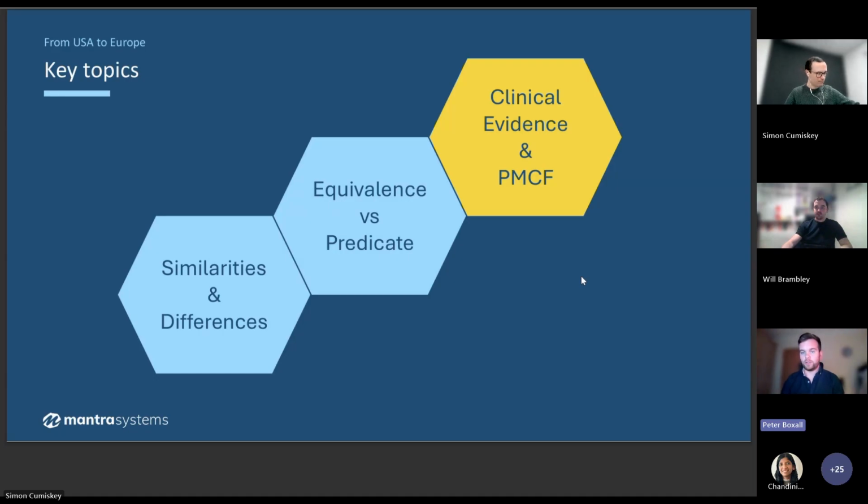And you can see that we can use this data to generate a quantitative assessment of overall benefit risk profile, and we need to show that that's favourable. It's clearly undesirable and impossible to remove all risk from use of a device, but we need to show that when risks are balanced against clinical benefit, the benefit risk profile is in favour of using the device.